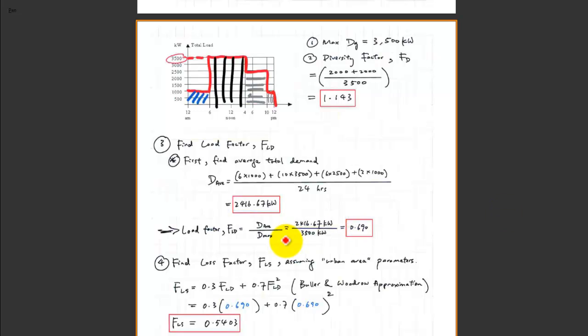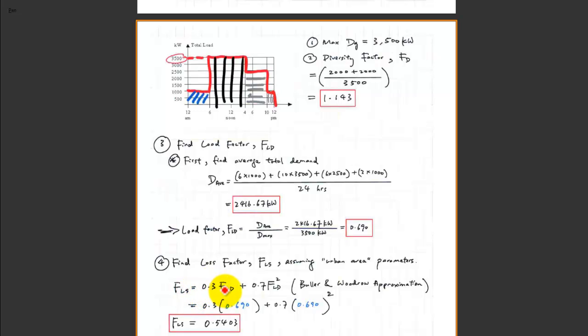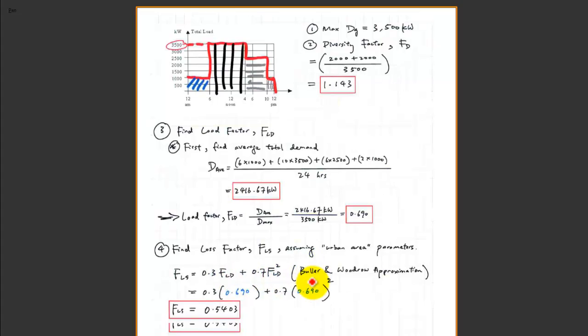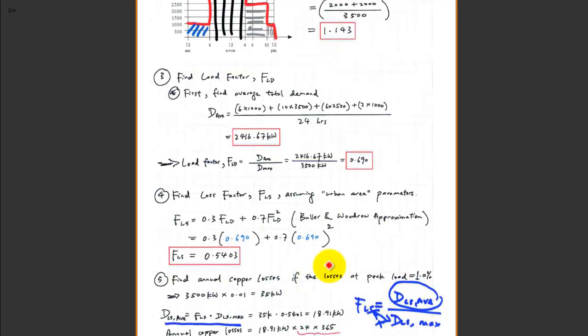This question also introduces a different approach to find the loss factor. Remember from last lecture, we discussed how you can infer the loss factor from the load factor. We know the load factor already. Assuming this is an urban area, we use the equation: 0.3 times load factor plus 0.7 times load factor squared. Plugging in the load factor value with those coefficients, the loss factor is estimated as 0.5403.